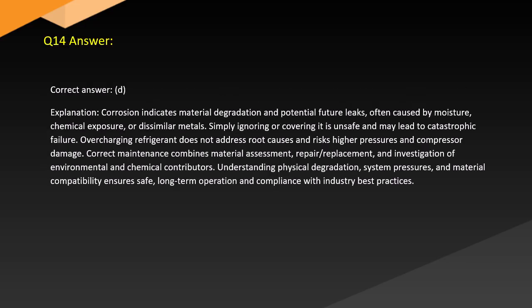Answer. Correct answer: D. Explanation. Corrosion indicates material degradation and potential future leaks often caused by moisture, chemical exposure, or dissimilar metals. Simply ignoring or covering it is unsafe and may lead to catastrophic failure. Overcharging refrigerant does not address root causes and risks higher pressures and compressor damage. Correct maintenance combines material assessment, repair or replacement, and investigation of environmental and chemical contributors. Understanding physical degradation, system pressures, and material compatibility ensures safe, long-term operation and compliance with industry best practices.